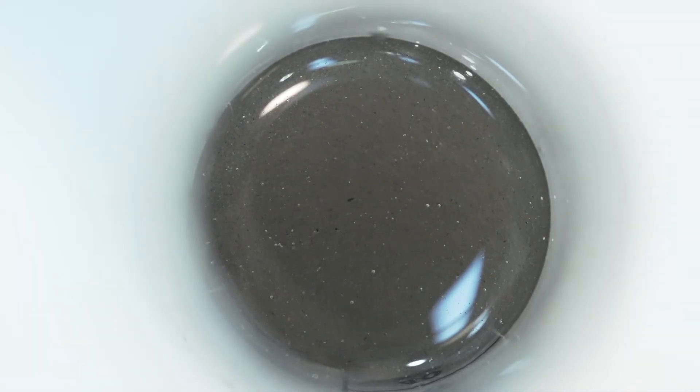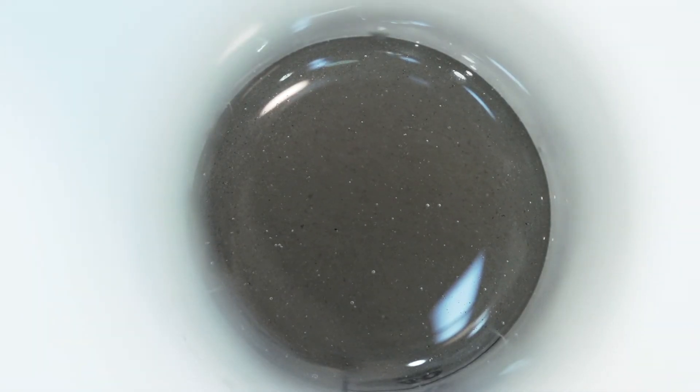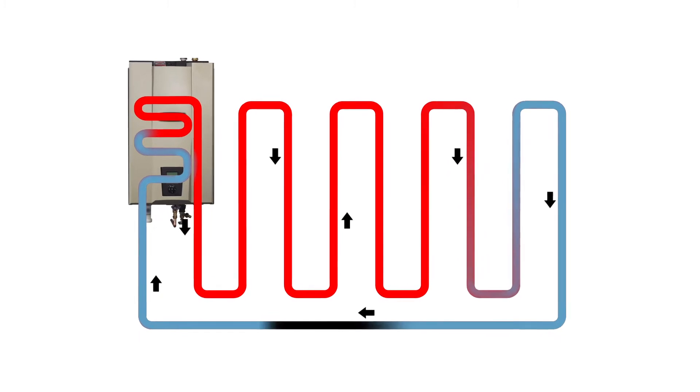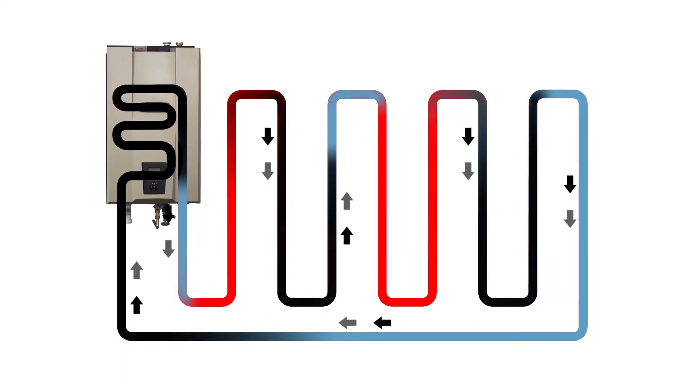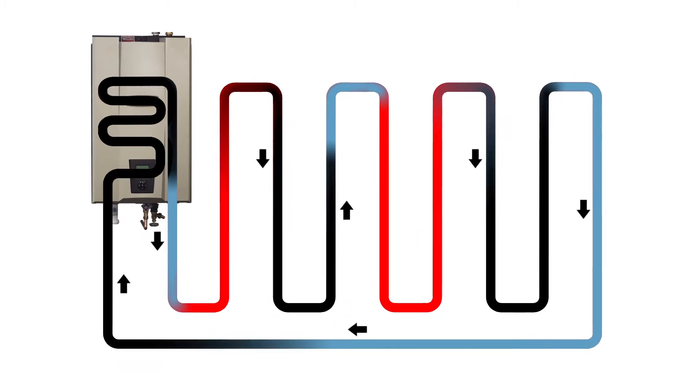If the water looks more like coffee and the circles aren't clearly visible, the system will need a good clean first. Whether the boiler is old or new, the last thing any customer or installer wants is dirty water flowing around it.